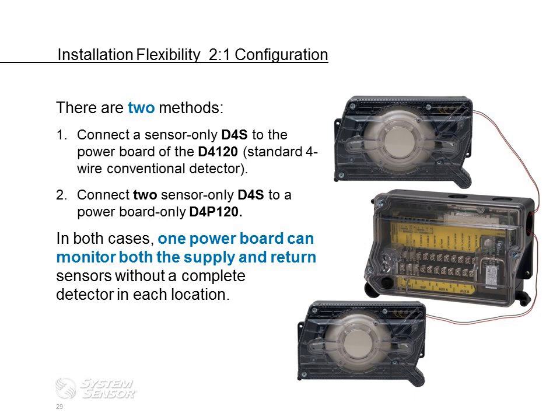Now, a lot of people ask, well, when would we ever do this? When would we ever see this kind of configuration? We see this configuration in some of the rooftop manufacturers because space is at a premium in their cabinetry. So this allows them to put the small heads out in the airstream and to remote them back to the power board. We've also seen it on field-installed applications where there's just not enough room for a full-size duct detector due to the size of the duct or the ability to get in it for work reasons.